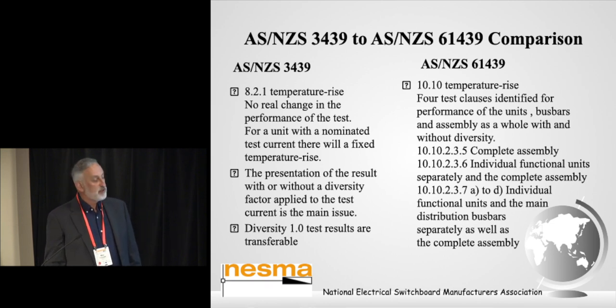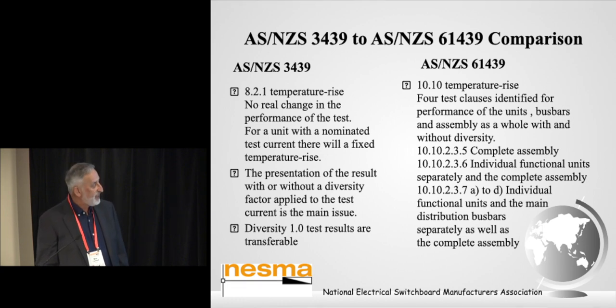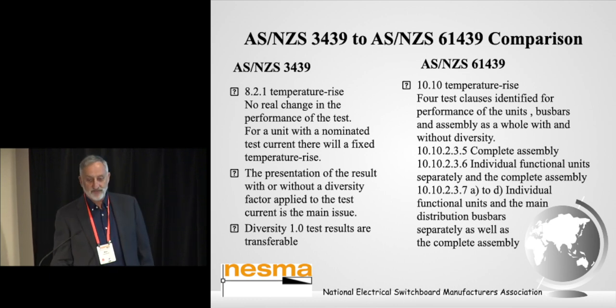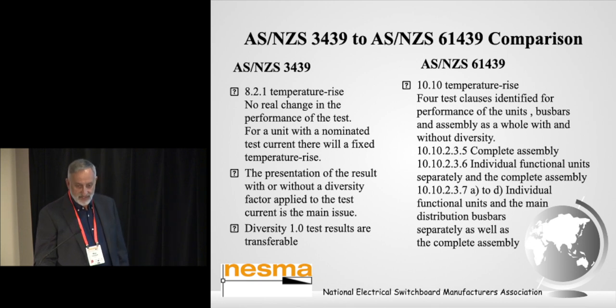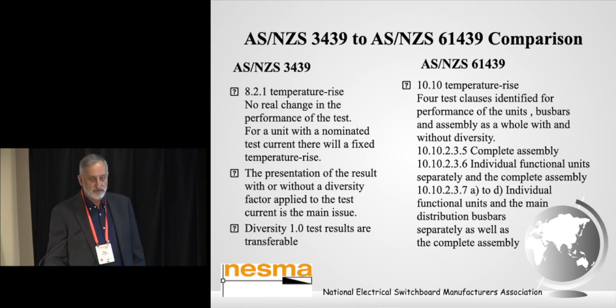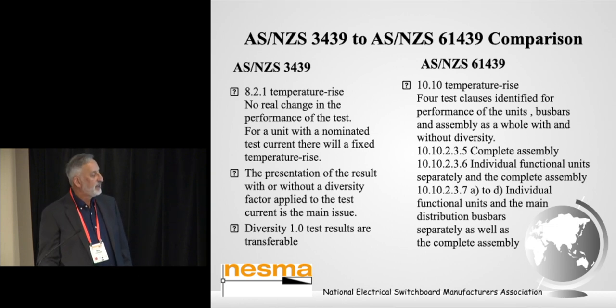We then look at temperature-rise test. One of the things I like to reinforce to people is that under this temperature-rise test there's no real change in the performance of the test, because I hold the opinion, and I believe it's irrefutable, that for a unit with a nominated test current, there is a fixed temperature rise that is attained. So if you've got a certain amount of current in a fixed box, with that current you will get that temperature rise for that unit, unless you start changing ventilation or something else, but it's a fixed quantity.